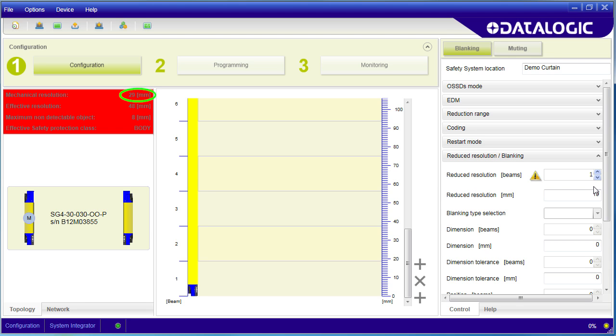by reducing the resolution by 1 we can now only guarantee detection of a 48mm object and have reduced this sensor safety class to body.